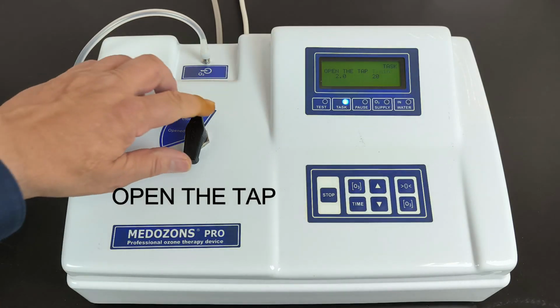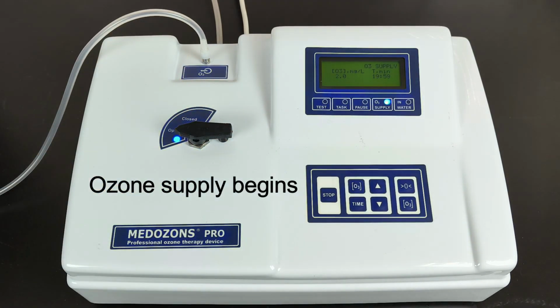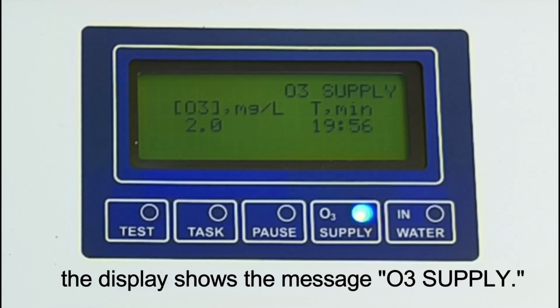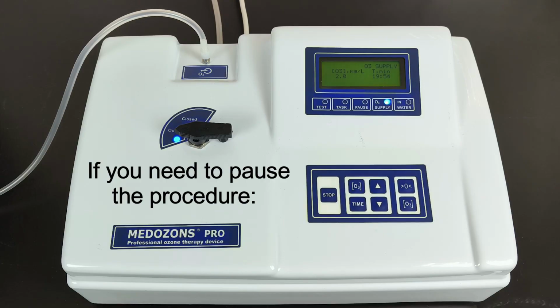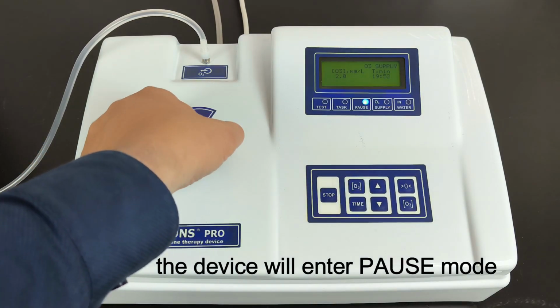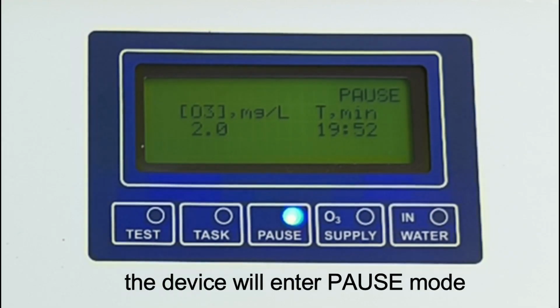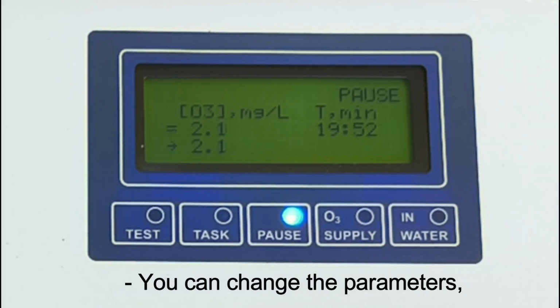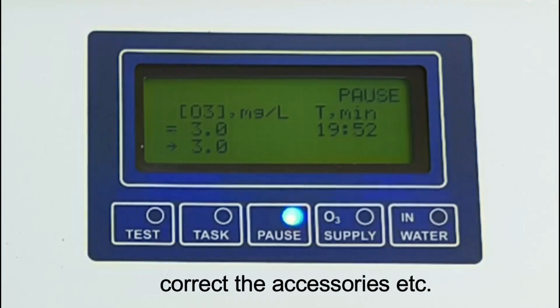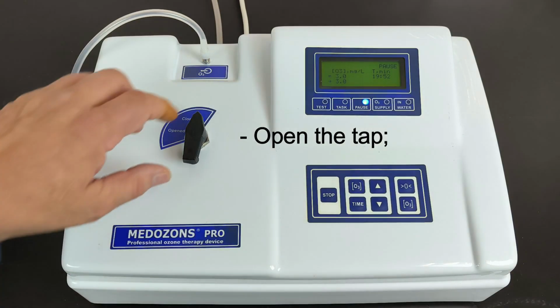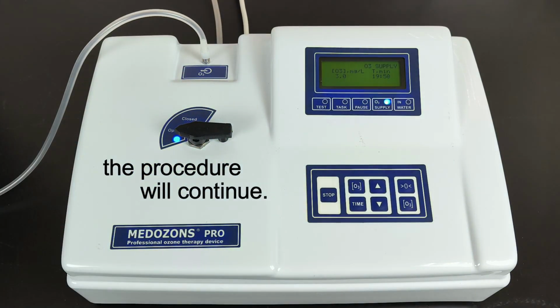Open the tap. Ozone supply begins, and the display shows the message O3 supply. If you need to pause the procedure, close the tap, the device will enter pause mode, and the timer will stop. You can change the parameters, correct the accessories, etc. Open the tap, the procedure will continue.